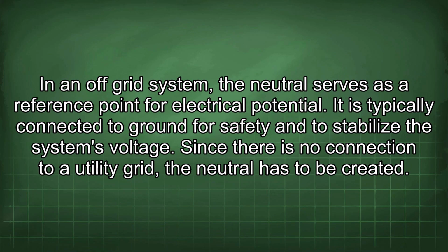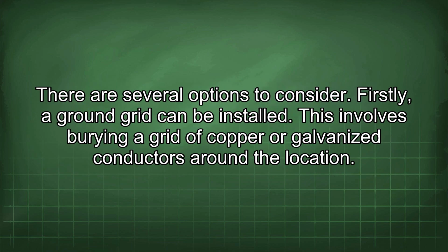In an off-grid system, the neutral serves as a reference point for electrical potential. It is typically connected to ground for safety and to stabilize the system's voltage. Since there is no connection to a utility grid, the neutral has to be created. There are several options to consider. Firstly, a ground grid can be installed.